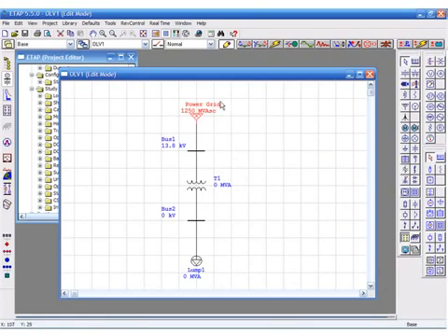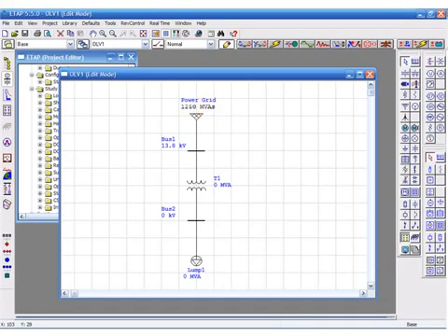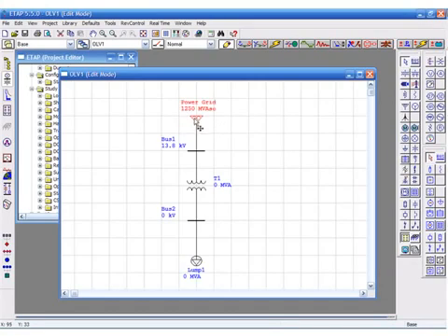The transformer percentage and X over R as we said before should be entered based on nameplate data. Typical data can be used if the transformer has not been purchased or the nameplate data is not available.